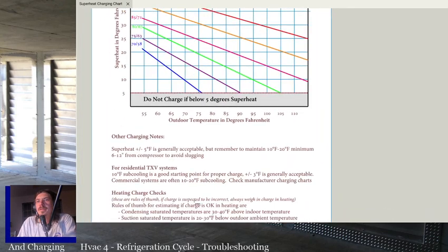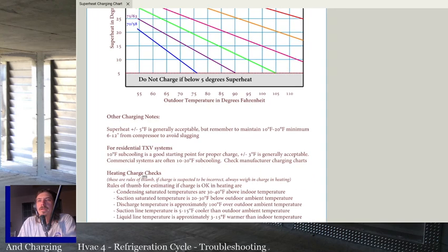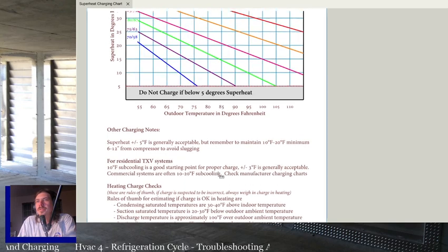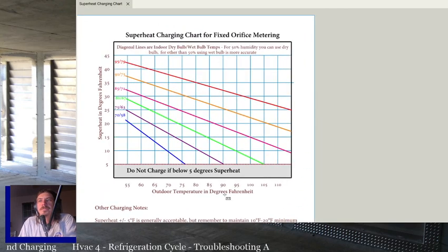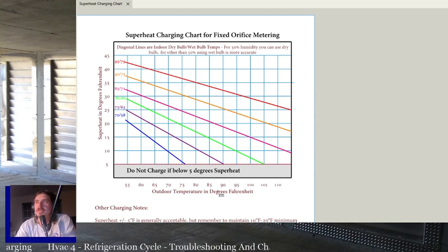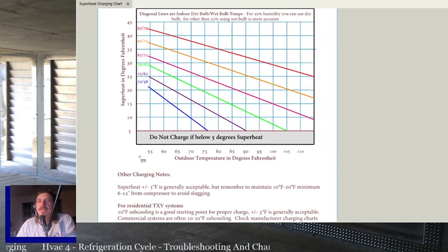I mean, obviously TXVs are a little easier. Heating charge checks are kind of tricky, but you've got some numbers to go off of. Superheat takes a little bit of practice to make sure you're doing everything right, checking everything right. And obviously, if you're doing a lot of fixed orifices, you should preferably have an in-duct psychrometer so that you can check wet bulb and dry bulb in the duct. The upside of that is you can perform all kinds of fun calculations. But for the most part, dry bulbs will usually get you close enough for most systems that you're going to work with. So there's your ways to check and charge.